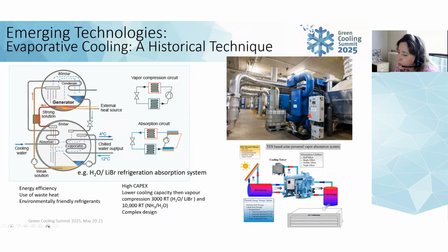Absorption systems, or thermal compression systems, use water-lithium bromide or water-ammonia as refrigerant-absorbent couple. Basically the refrigerant absorbs the heat. I'm trying to explain this figure, but I'm sorry, I'm not able to use the pointer, so I will try to explain it to my best. Basically the refrigerant absorbs the heat from the water loop in the chiller, and then it gets absorbed by the absorbent. The mixture is then driven to the generator at the top, where refrigerant and absorbent get separated by increasing their pressure through applying an external heat source. Once separated, the refrigerant releases heat into the environment through the condenser that you can see at the top of the generator.